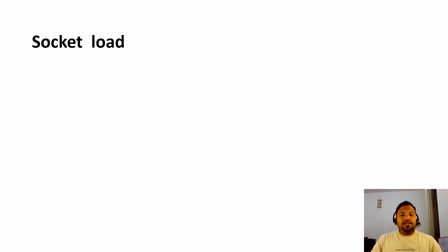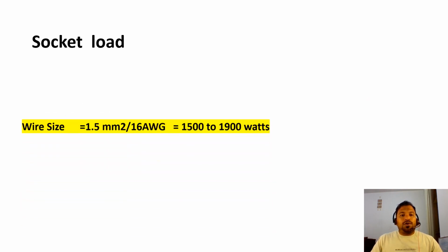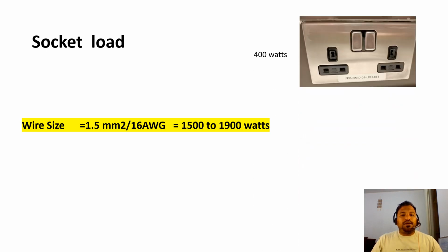Next we will see the socket load. For sockets, the wire size is similarly 1.5 mm square, and you can load 1500 to 1900 watts.